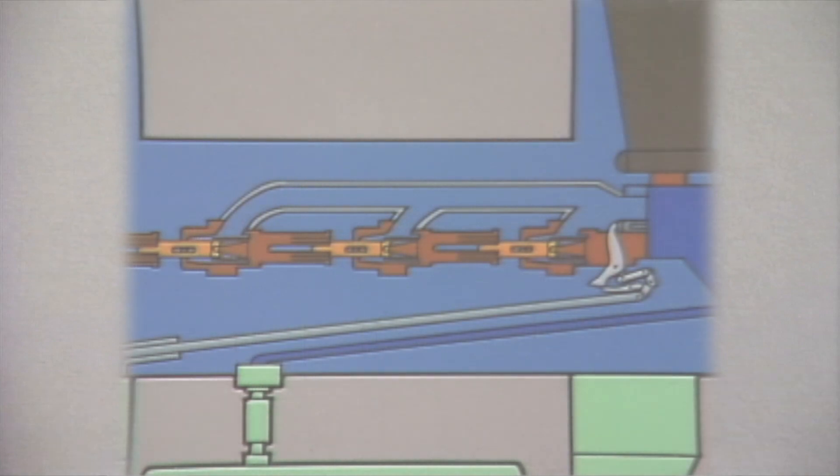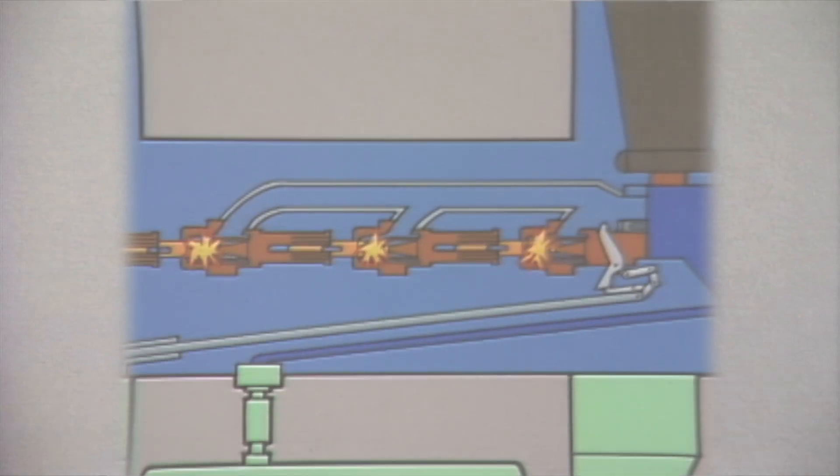When the breaker trips, the contacts separate and arcs form. At the same time that the contacts separate, the blast valve opens. This allows high pressure gas to blast through the blast tubes and through the arcs, blowing out the arcs.